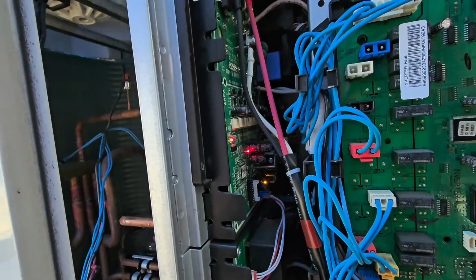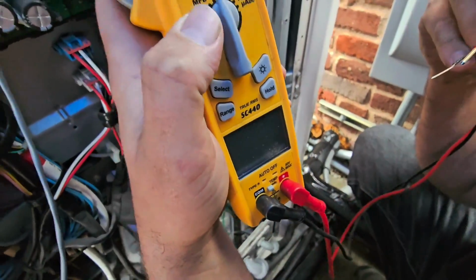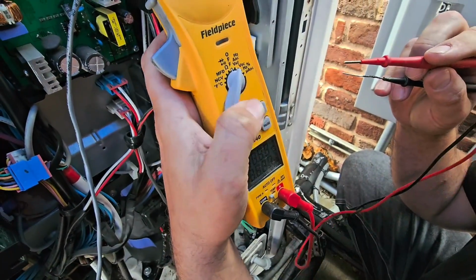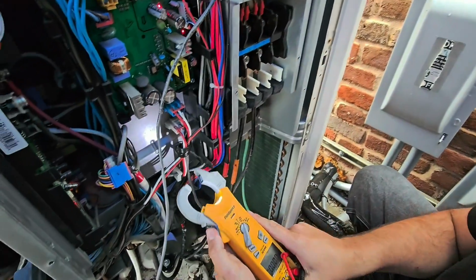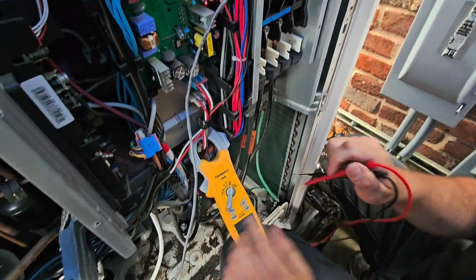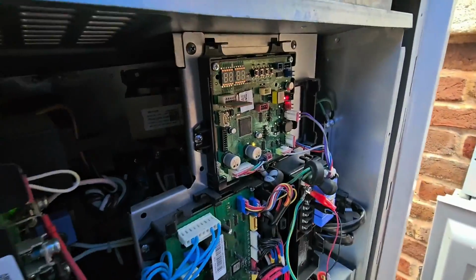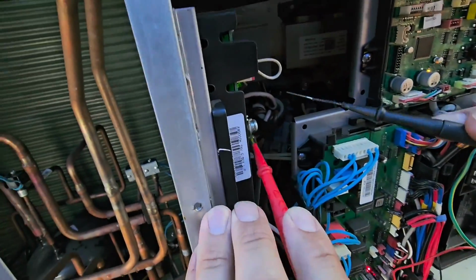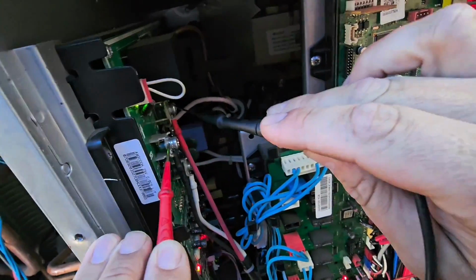Inverter boards are blinking. Now I'm going to take my meter and turn it to volts DC while it's running and while we don't have an error code. And then I'm going to go from this top inverter board to the black and red wire. Look what we got down there.